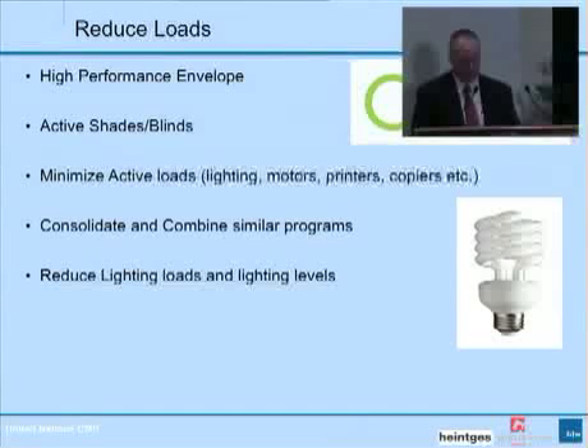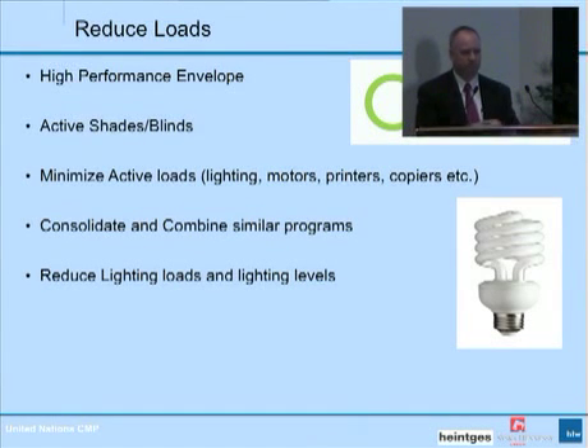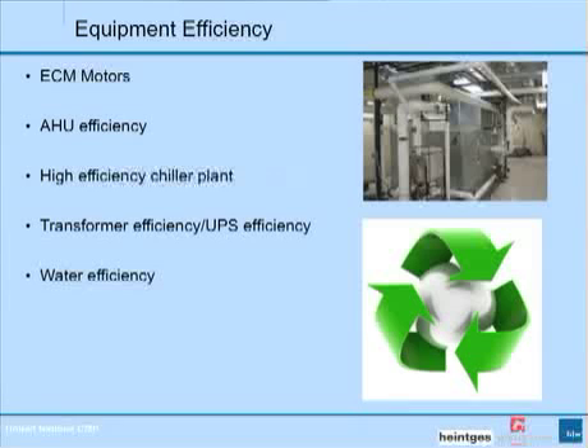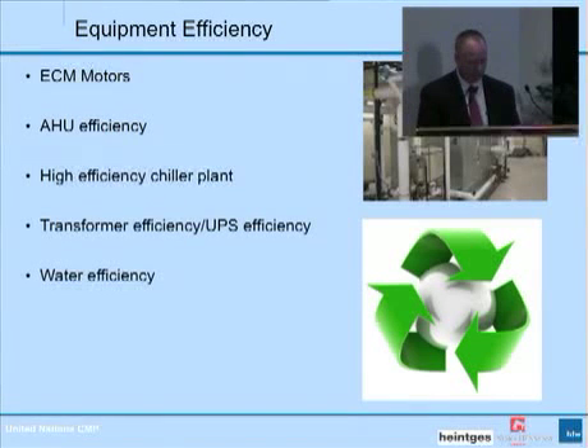We consolidated and combined similar programs. As I said before, the UN is a very flat organization. Each program unit would have their own miniature component of the server, their own storage section. Part of the program is to bring together some of these disparate programs to create both space efficiency in the campus and energy efficiency. Down to the component level, we used ECM motors for any of the larger motors above 5 horsepower on campus. We take a close look, and our specs are written to squeeze efficiency out at the component level for our air handling units, the chiller plant, transformers, and other equipment.